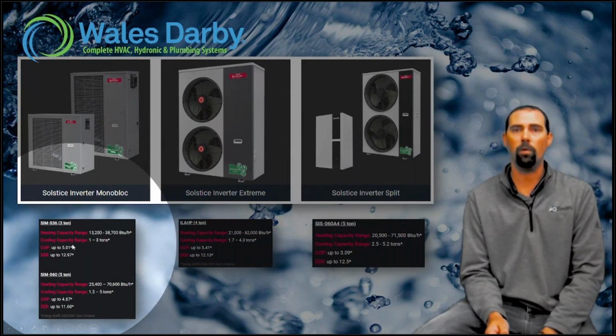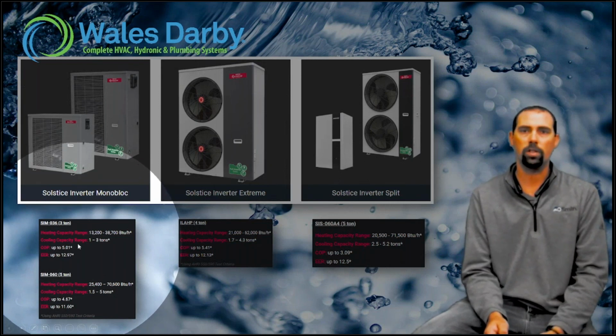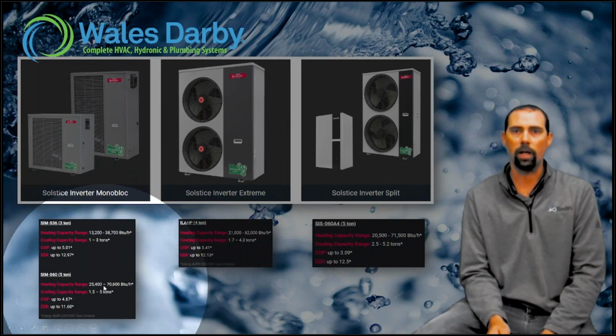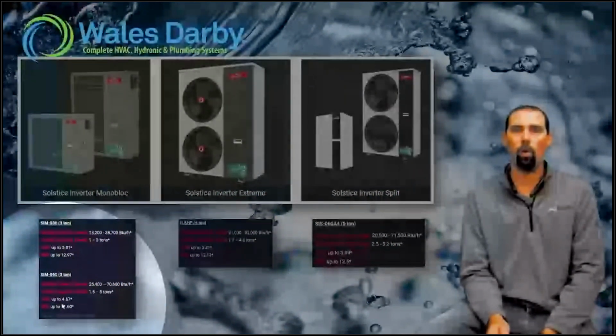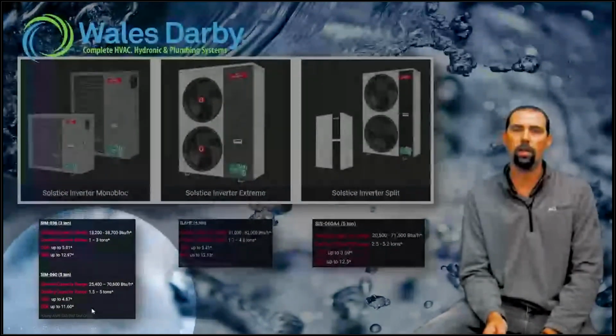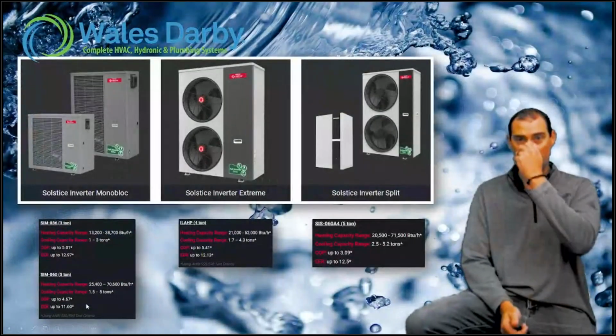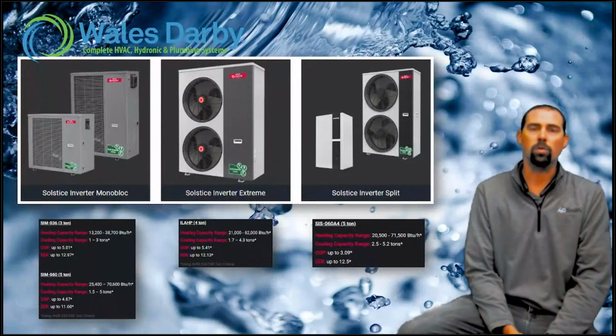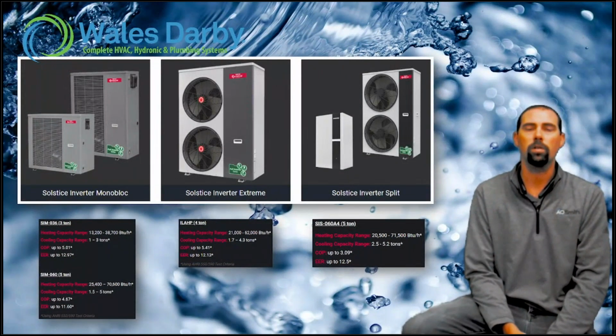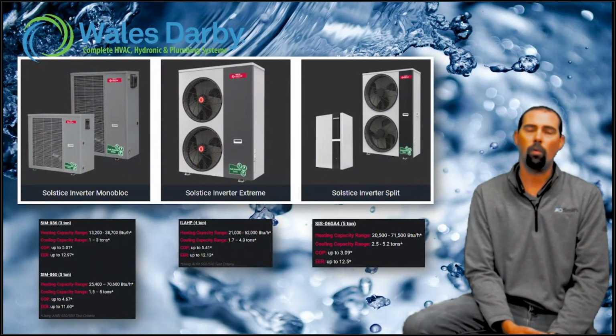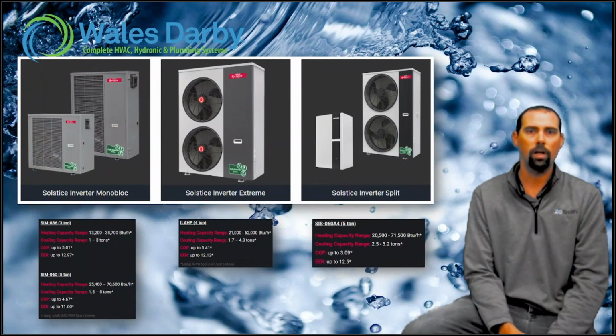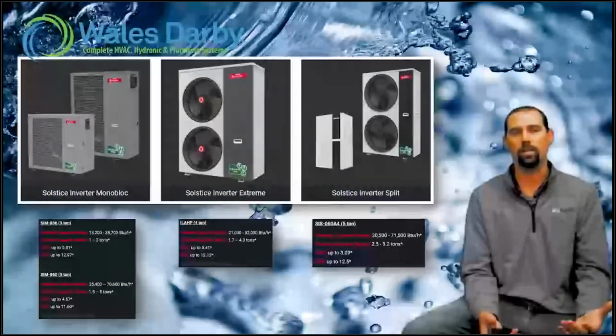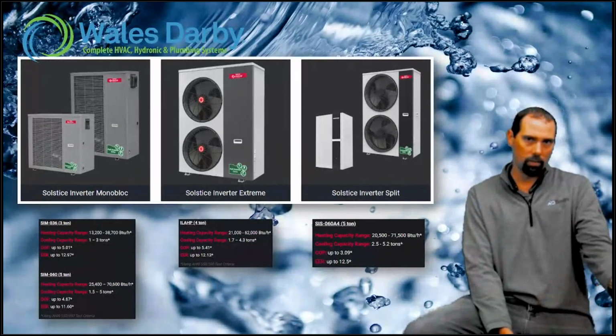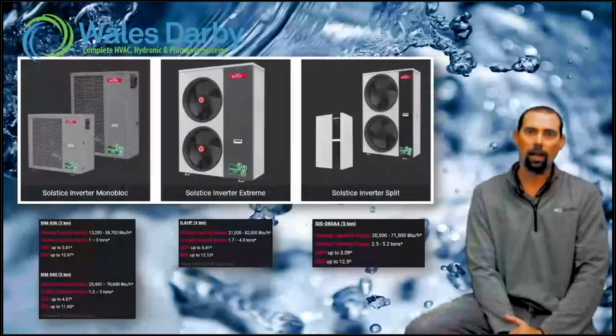If you take a look at some of those COPs we were talking about before, we're up to 5.01, and there's a little star there, so we've got to understand what that's coming from, and 4.67 it looks like, a little far for me to see, but those are high numbers when we talk about COPs and heat pumps. We need to understand at what water temp that is, what outdoor temp that is, these are design conditions in most cases. So we want to see how many BTUs we're actually getting out of the system.